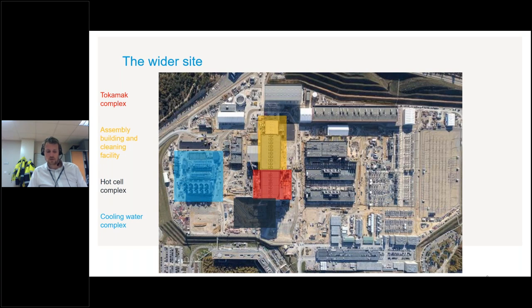The cooling water plant supplies a flow of over 33 meter cube per second. It has a chilled water system, a bespoke tokamak cooling system, and a heat rejection system. You can see some of the fans that are part of the heat rejection system, and it supplies all of the buildings and plant.